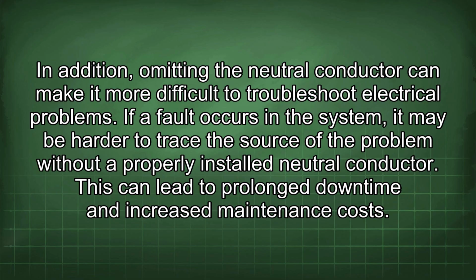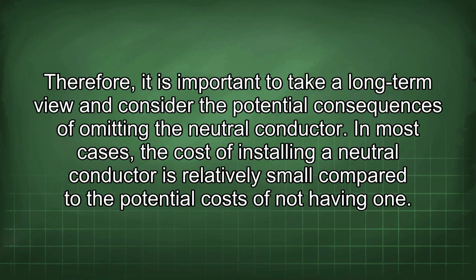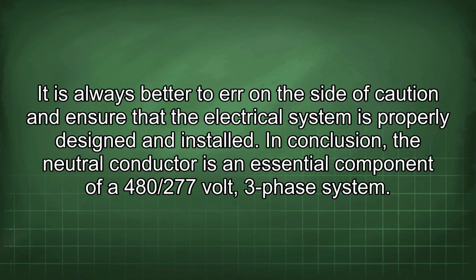In addition, omitting the neutral conductor can make it more difficult to troubleshoot electrical problems. If a fault occurs in the system, it may be harder to trace the source of the problem without a properly installed neutral conductor. This can lead to prolonged downtime and increased maintenance costs. Therefore, it is important to take a long-term view and consider the potential consequences of omitting the neutral conductor. In most cases, the cost of installing a neutral conductor is relatively small compared to the potential costs of not having one. It is always better to err on the side of caution and ensure that the electrical system is properly designed and installed.